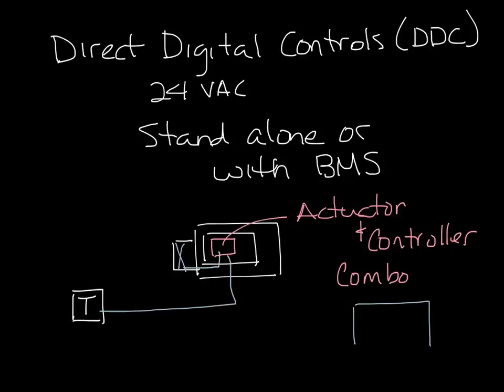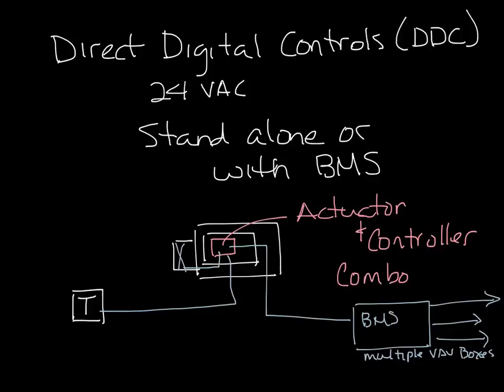The difference here from analog is that there's a building management system somewhere, so there's a computer running software that is connected to this VAV box controller, and also to multiple VAV boxes so that you can see your entire system sitting in an office somewhere, or maybe off-site. DDC controls are the most common controls we see today.